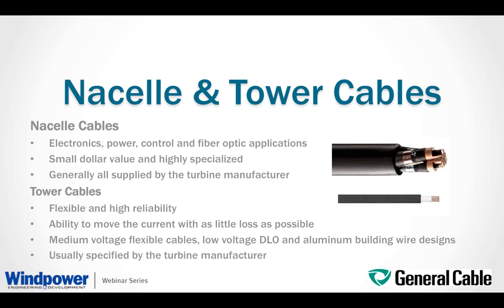Then in the tower, again, flexibility is very important. Also, as Brendan pointed out, there's consideration made to moving the current down with as little loss as possible. Depending on the turbine manufacturer design and where the transformer is located, up in the nacelle or down at the bottom, a medium voltage or low voltage flexible cable is going to be used. To maximize flexibility, soft annealed copper flexible stranding is typically used. The flexible medium voltage cable is typically a 35 kV design similar to a mining cable or SHD portable power cable design. On the low voltage side, you would typically use the 2000 volt DLO EPR cross-linked CPE insulation jacket design.